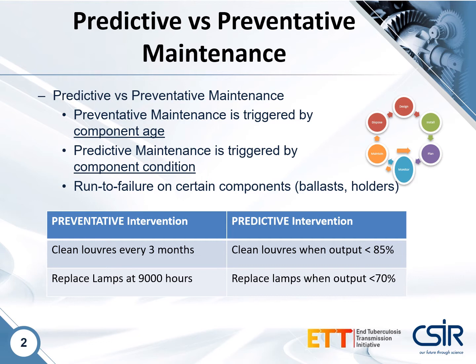For instance, typical preventative maintenance interventions you would have heard of would be, for instance, to clean the louvers every 3 months or replace lamps at every 9,000 hours, regardless of the condition, whereas the predictive maintenance strategy would require cleaning of louvers at intervals found to drop device output by 15%, or to only replace lamps where the output has dropped by more than 30%.